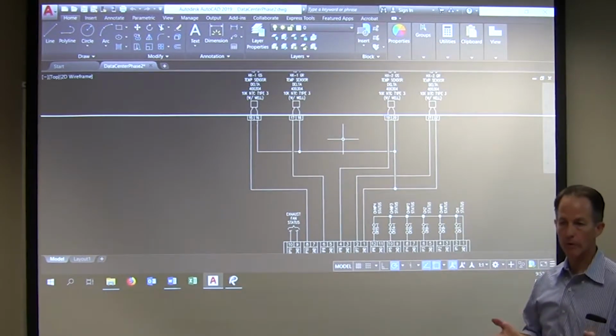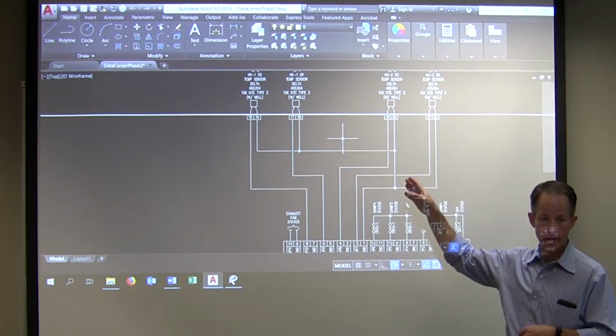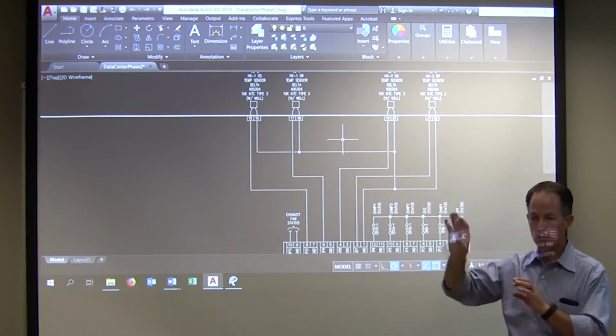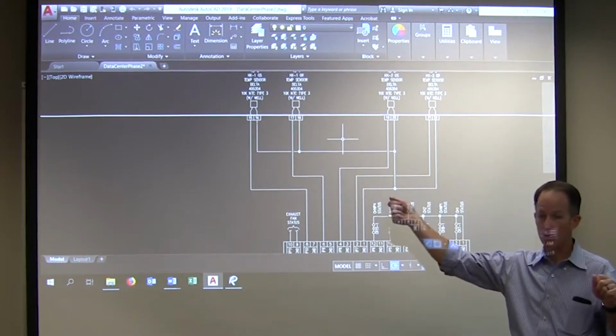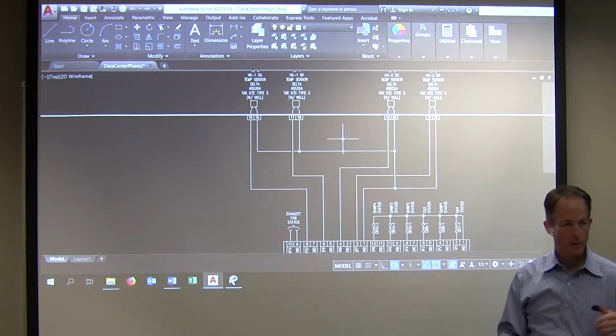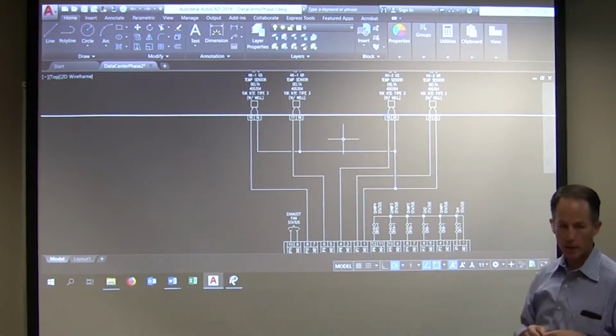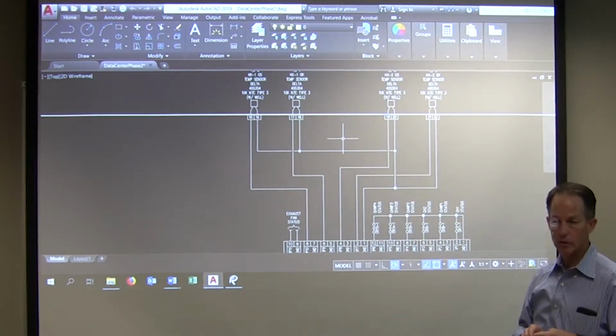Resistance. Okay, we're going for resistance, right? Because we're not powered on the circuit right now. This is just a raw sensor, just happens to be at a very long length of wire, right? Maybe it's 300 or 400 feet out there. Okay, so I put my meter on there. If I was running 45 degrees, what should I read?